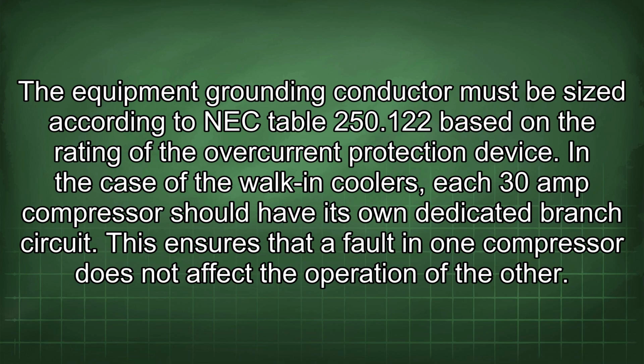In the case of the walk-in coolers, each 30 amp compressor should have its own dedicated branch circuit. This ensures that a fault in one compressor does not affect the operation of the other.